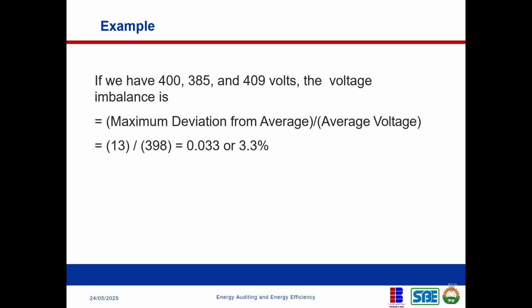Maybe a certain load is concentrated on one line, the blue, yellow, or red phase. If too many loads are concentrated there, it affects the voltage across that line, and the other two lines will have lesser voltage because they have lesser load. So what needs to be done is to move some of the load from the overloaded line, spread it out, and keep monitoring the voltages until they're evenly distributed. You may not get a perfect balance, but the variation shouldn't be so much that it affects the functioning of your equipment.